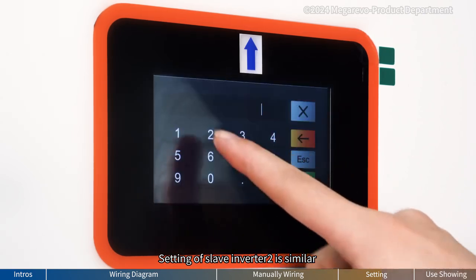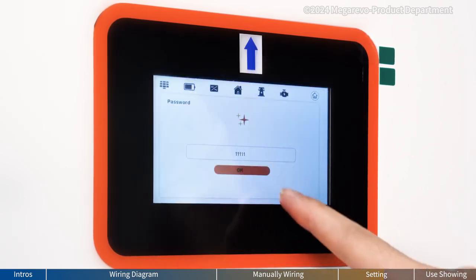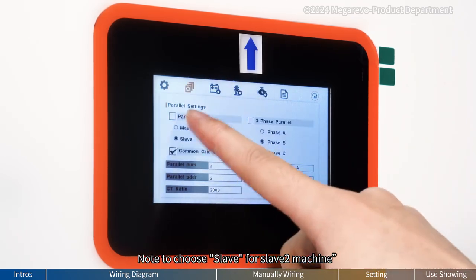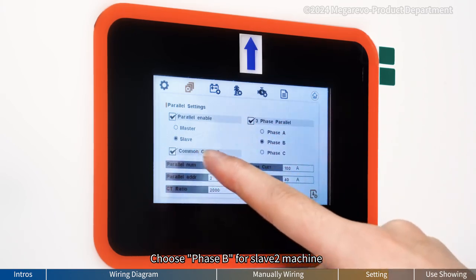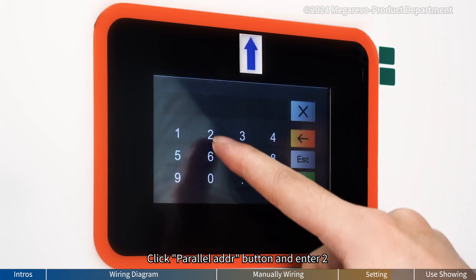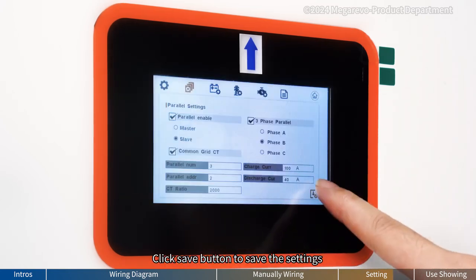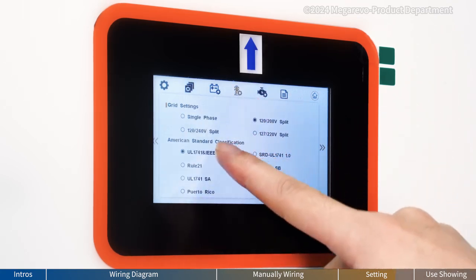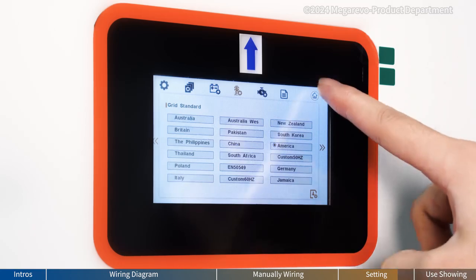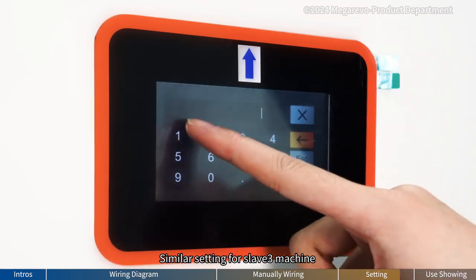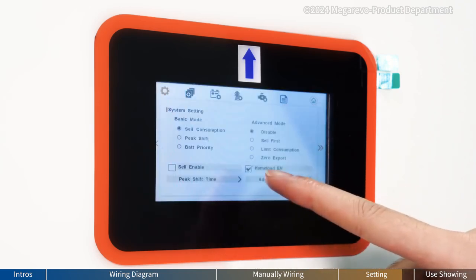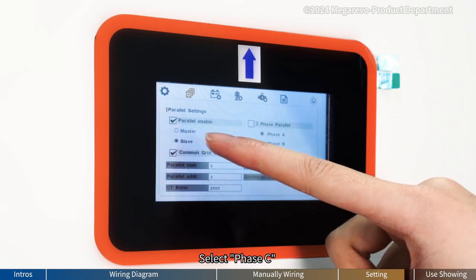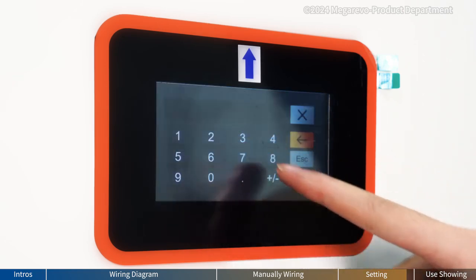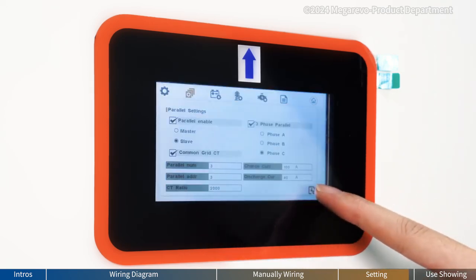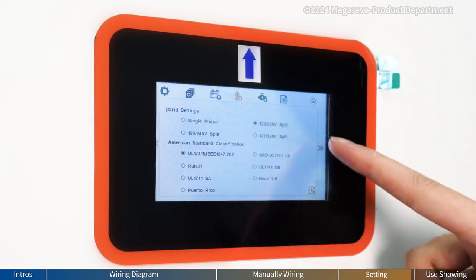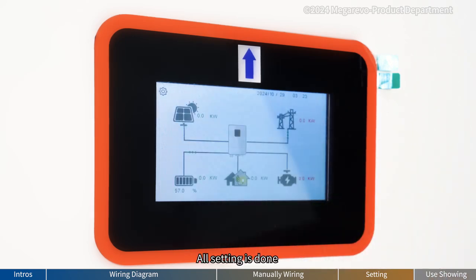Setting of Slave inverter 2 is similar. Now choose Slave for the Slave 2 machine. Choose phase B for the Slave 2 machine. Click Parallel Address button and enter 2. Click Save button to save the settings. Similar setting for the Slave 3 machine. Select Slave. Select phase C. Enter 3 for the parallel address. All settings are done.